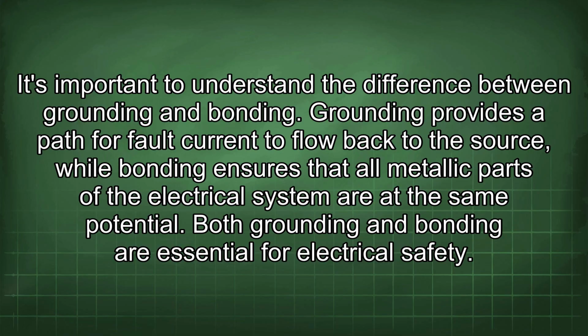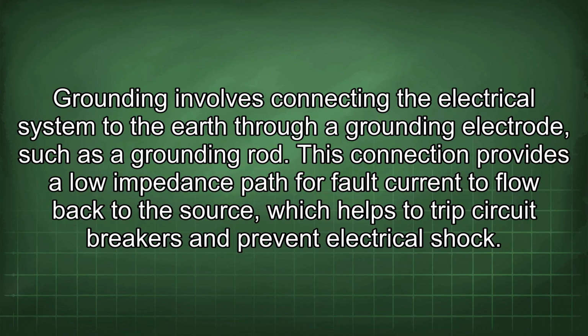Grounding provides a path for fault current to flow back to the source, while bonding ensures that all metallic parts of the electrical system are at the same potential. Both grounding and bonding are essential for electrical safety. Grounding involves connecting the electrical system to the earth through a grounding electrode, such as a grounding rod. This connection provides a low impedance path for fault current to flow back to the source, which helps to trip circuit breakers and prevent electrical shock.